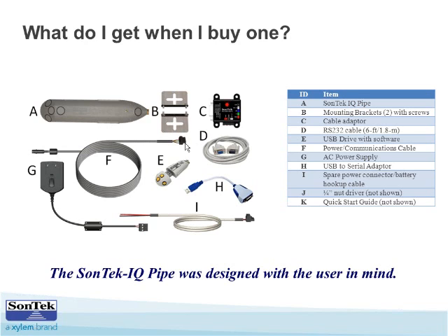Well, one great thing that they did with this is made it smaller. Typically, with the larger connector, the wet mateable connector on the prior series, you were looking at 1.5 inch, 1.25 inch conduit if you wanted to provide some mechanical protection for the device when you're installing it. This cable now in the instrument is much narrower. So maximum size of conduit that you're dealing with, if you want to provide mechanical protection, is only 1 inch. You'll probably even get away with 3/4 inch if you just pulled in one direction.